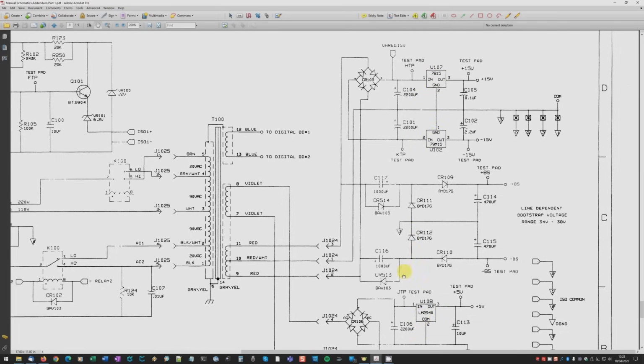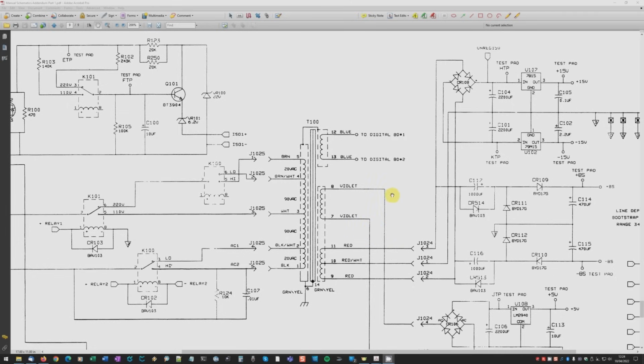They would all just go haywire. So I probably think that's what's happened in this case. So for the testing of the analog board, I'm certainly not going to hook up the transformer. What I'm going to do is inject my own voltages here. I'm probably going to inject plus 15, minus 15 volt directly, because the regulators are removed at the moment, and that way I can have good control over the DC voltages powering the analog board.